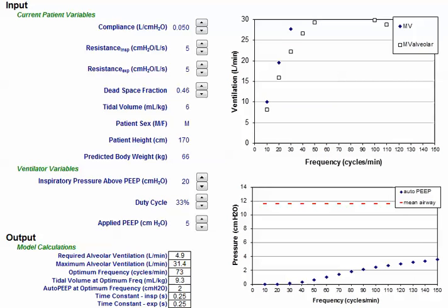For a given level of applied pressure or pressure control setting, there's a max value for my tidal volume or minute ventilation. If I multiply this inspiratory pressure of 20 by the compliance of 50, I should get a max obtainable tidal volume of 1 liter, and a max obtainable minute ventilation based on my respiratory rate multiplied by that max tidal volume I can get.